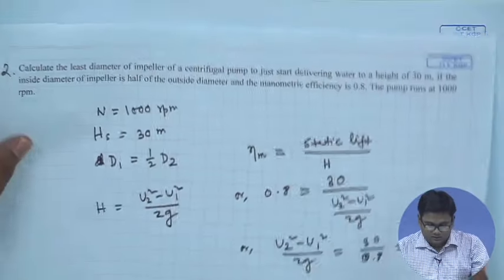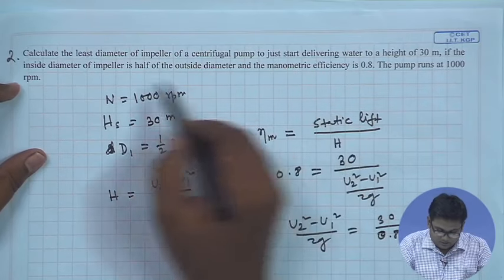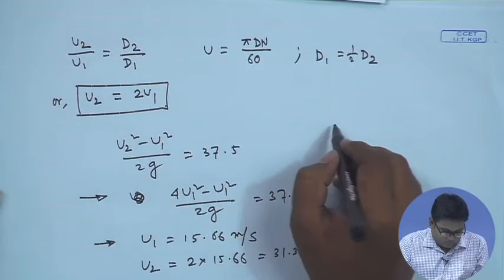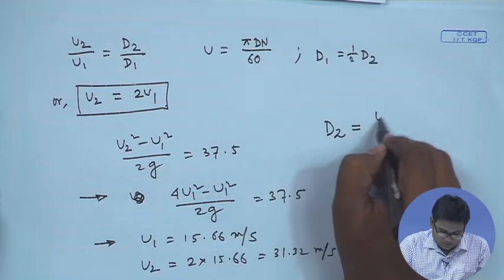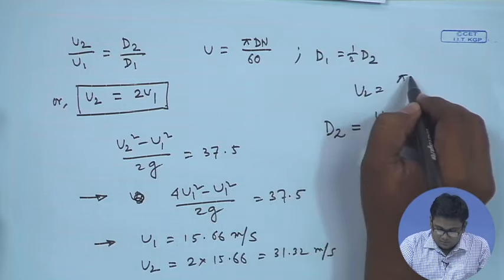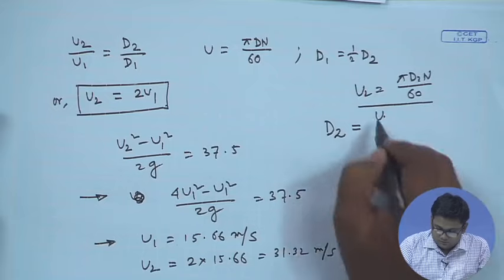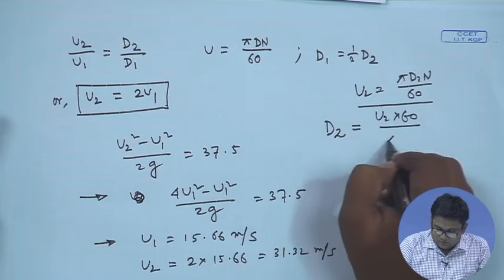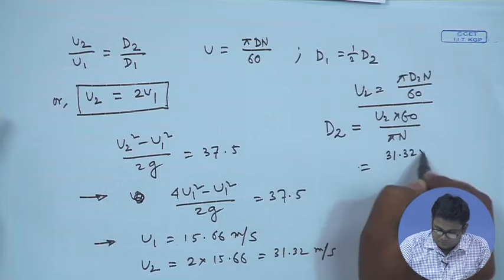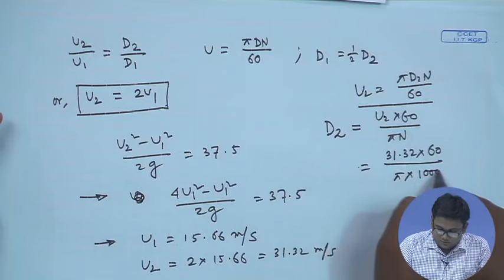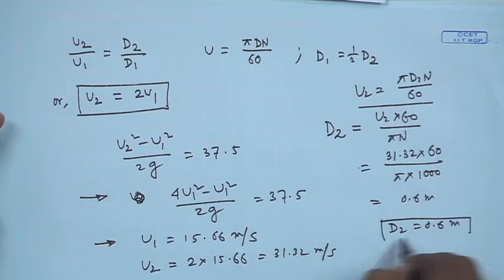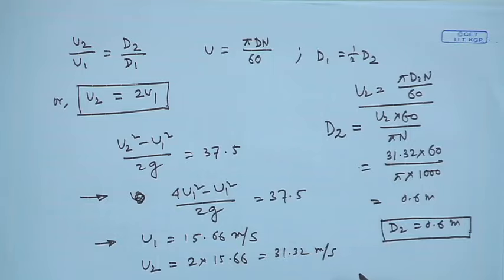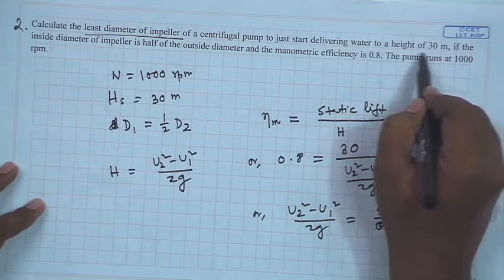The outer impeller diameter is found from u2 = π D2 n / 60, so D2 = u2 × 60 / (π × n) = 31.32 × 60 / (π × 1000) = 0.6 m. This is the least outer diameter of the impeller required to deliver flow with a static lift of 30 m. With this, I am ending today's lecture. Thank you.